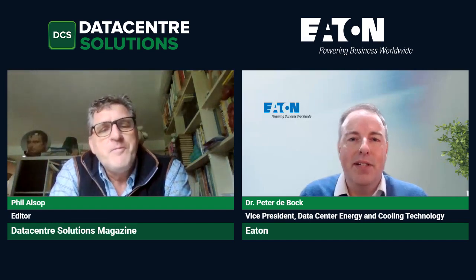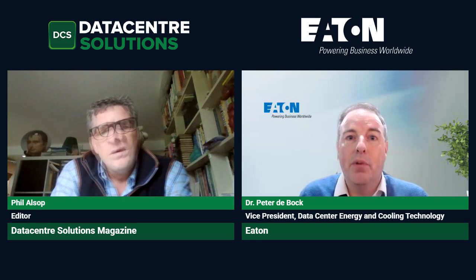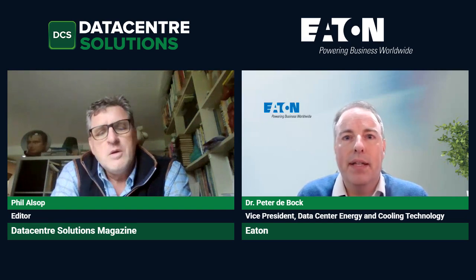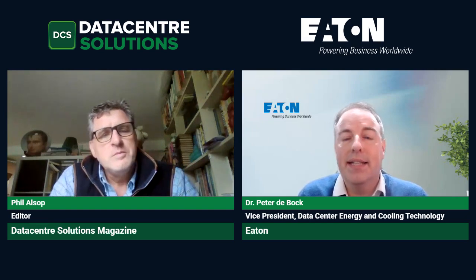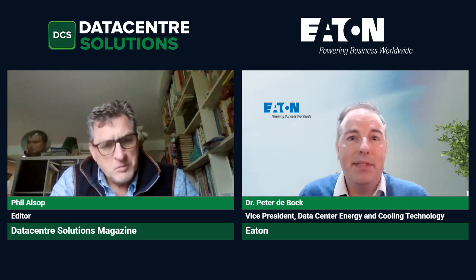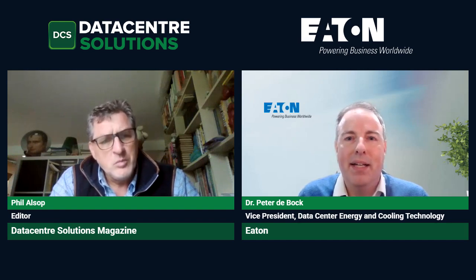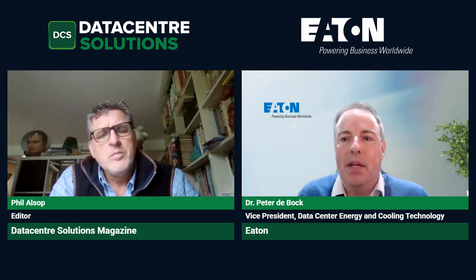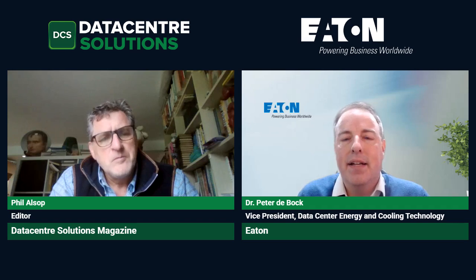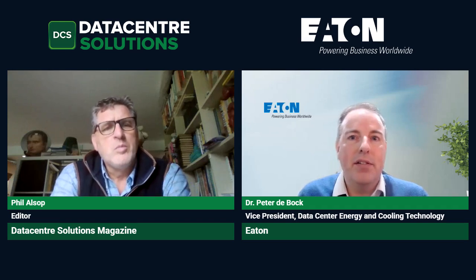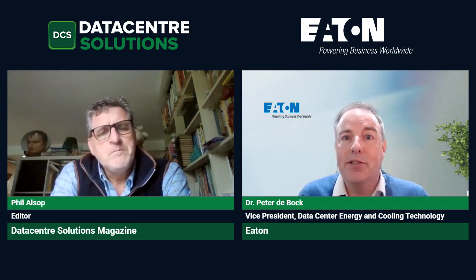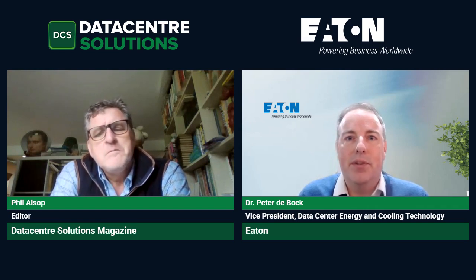That's a great question. When you're looking at NVIDIA Rubin and NVIDIA Rubin Ultra, we're looking at server racks that can exceed 100 kilowatts per rack, perhaps even go to 600 kilowatts per rack. In my opinion, that's a paradigm shift in data centers as we know it from the last decades, where traditional data centers are really focused on enterprise solutions that are 10, 20 kilowatts per rack at most.